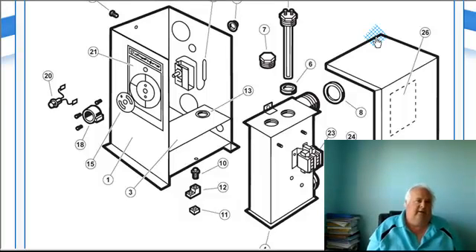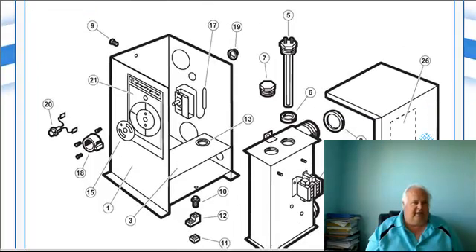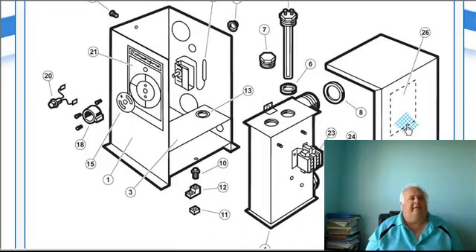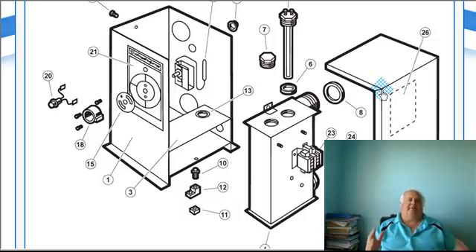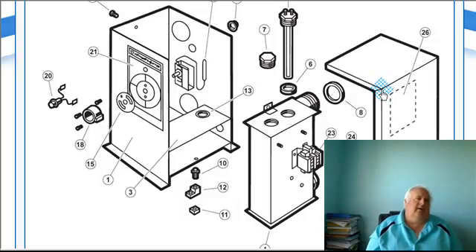I'll send you a link to, if you don't have a voltmeter or amp probe, to work on your stuff, you need to. But everything in this C-Spa is quite easy. Now, I wish I had a wiring diagram. My theory is where the power stops, the problem lies. Now, I'm almost positive that voltage goes into the top or the bottom of the contactor. I forget where. So you need to check for voltage at the contactor.